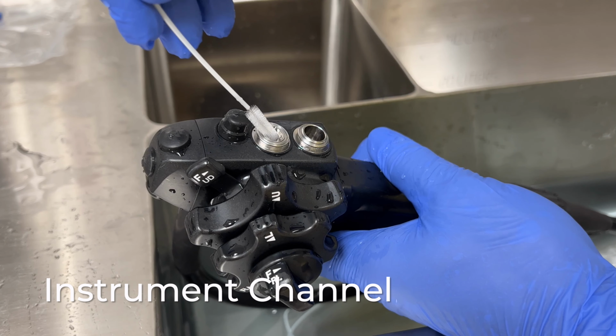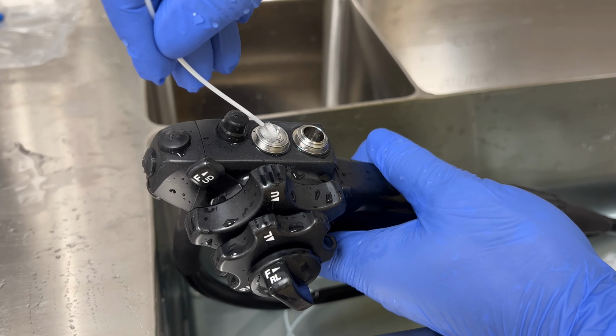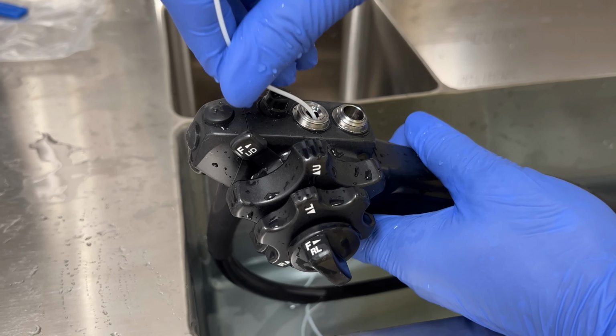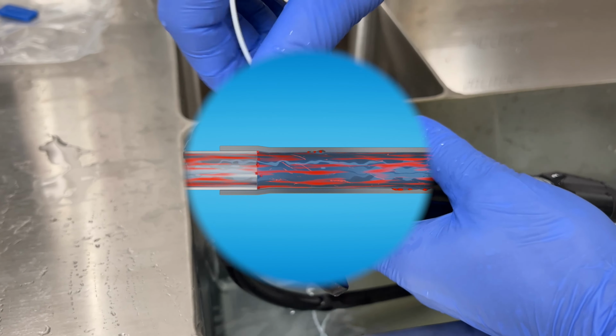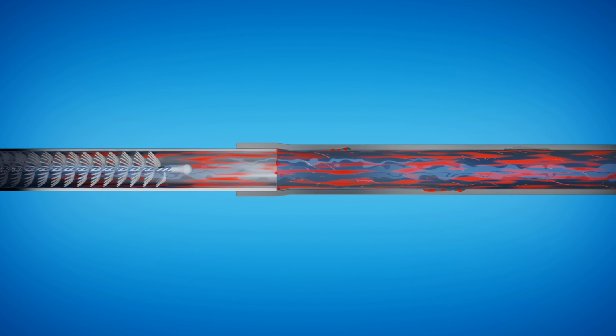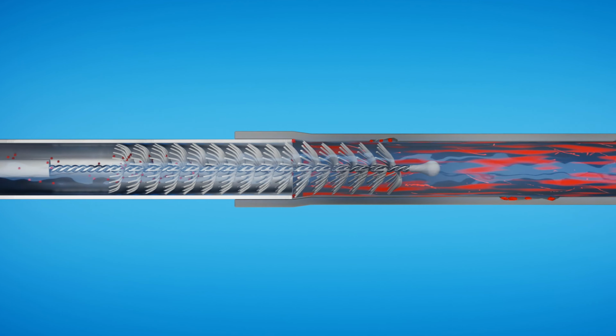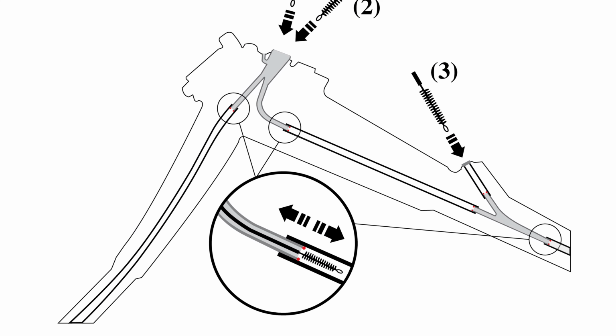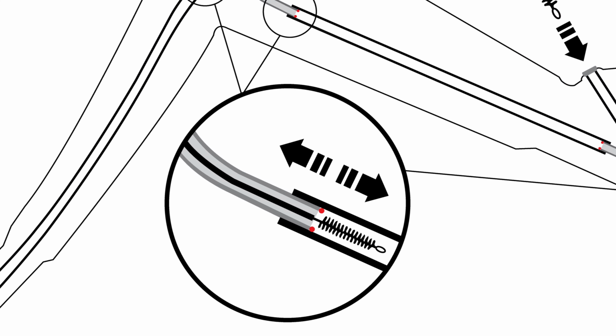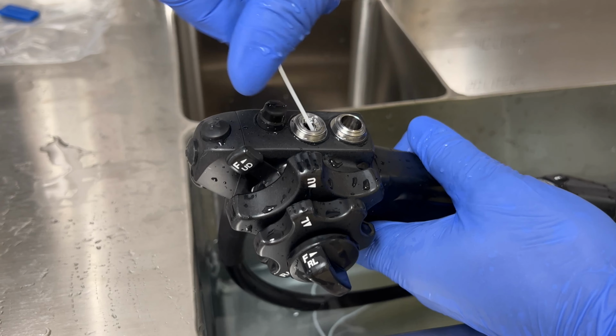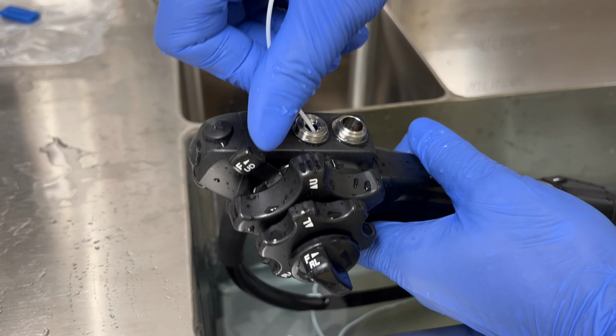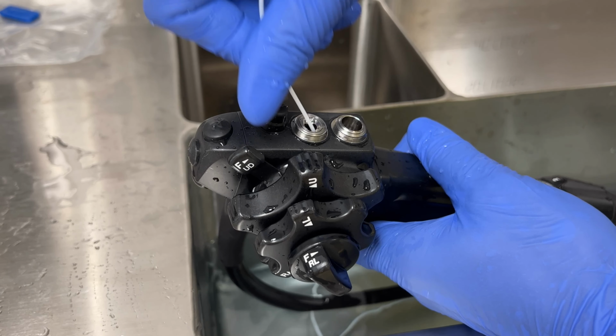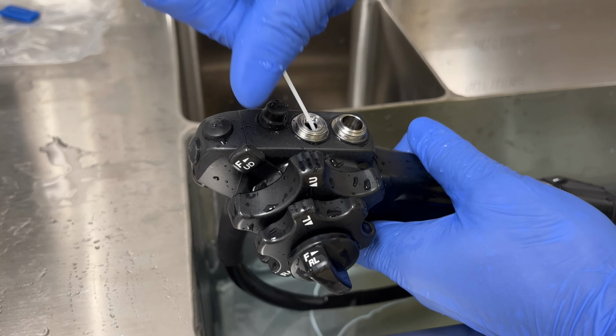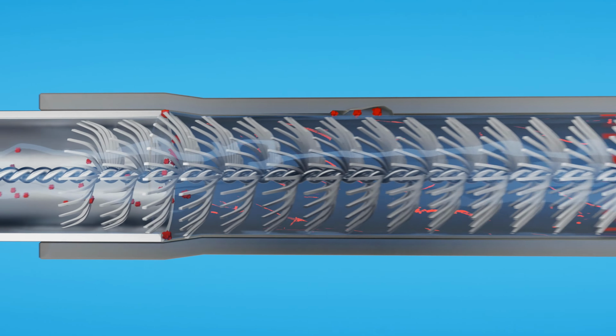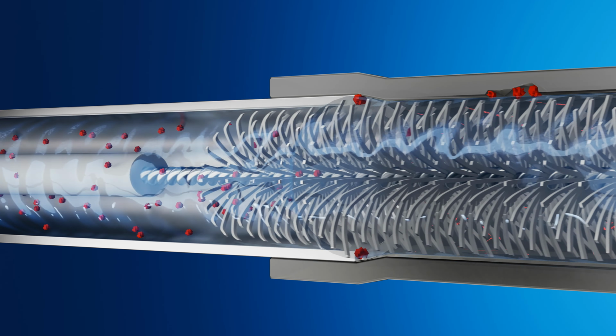The leading brush is carefully introduced into the instrument channel and gently pushed towards the area in the control body of the endoscope where the metal tube joins with the Teflon channel tube. Debris collected on the rim of the metal tube must be meticulously removed with the leading brush. The back and forth motion of the leading brush effectively dislodges and removes debris collected on the rim of the metal tube. Squeegees alone cannot accomplish this task.